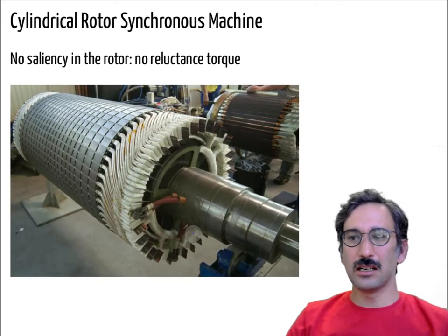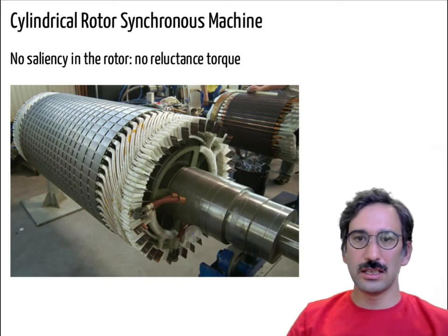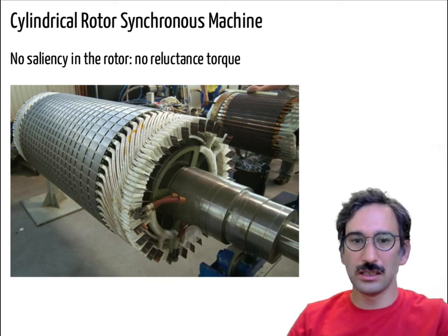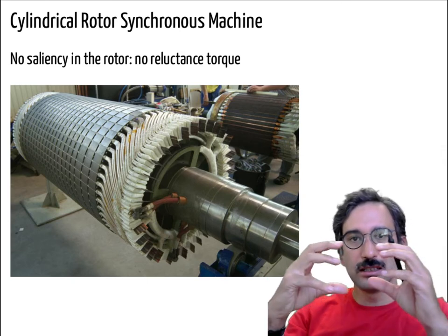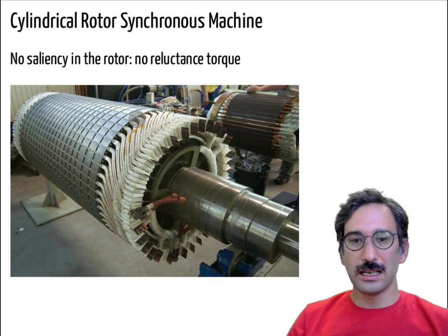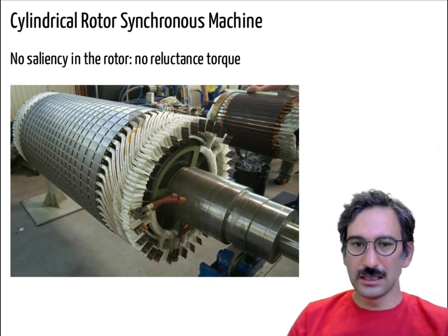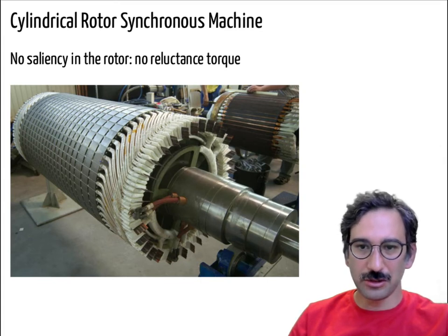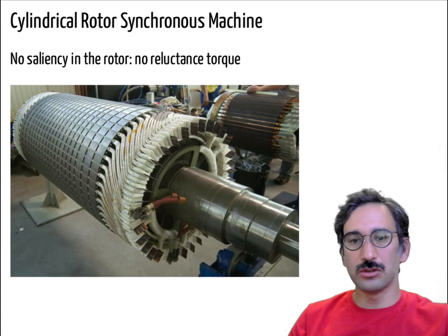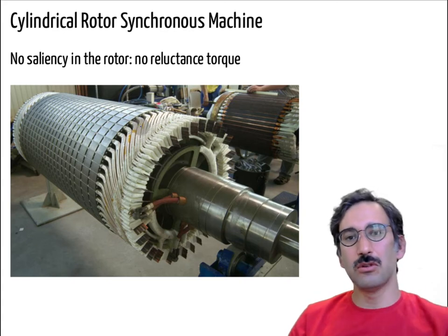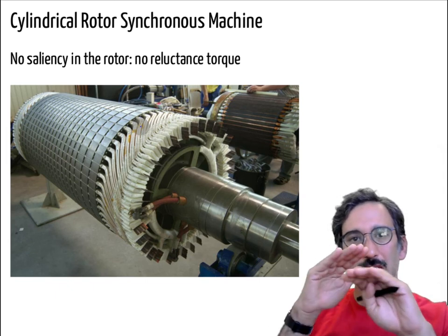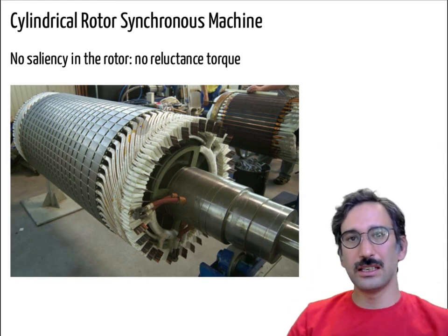So let's see a couple of examples. Here you see a normal cylindrical rotor machine. I don't know the application, but it's probably a high speed machine. So it has a small diameter and a long axial length. And again, you can see there are some places to put those windings, but normally the surface is quite cylindrical.